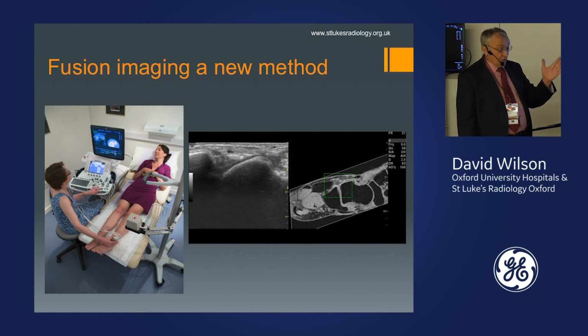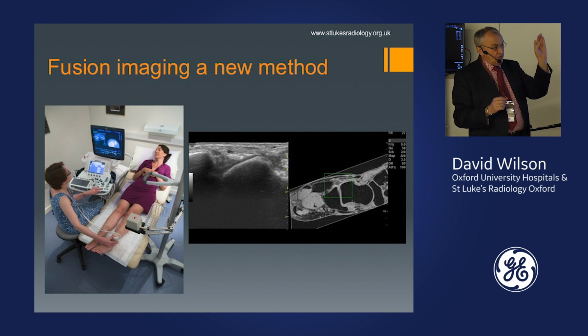So the fusion is: lock the plane, find 1 point on each picture which is the same, click on it, and the fusion is connected. Then you check. This is important if you're going to put needles in, because you want to be sure that the 2 planes are exactly the same. So look around, look at other subjects, rotate to a different angle, make sure that the same structures appear on the 2. If in doubt, you can re-register. You can find another point, click again. Usually you don't need to. Usually it's locked at that point and you're pretty accurate at that stage.